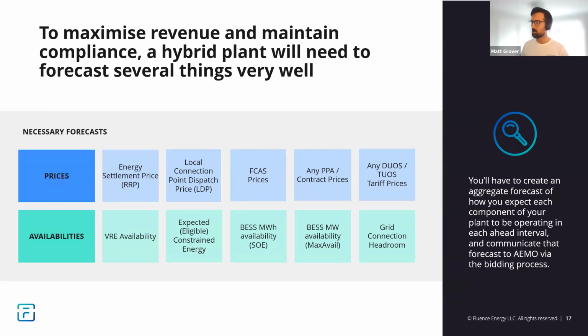One of the main new aspects of hybrid plant operation is that many hybrid plants are going to share a grid connection. So you might have a 100 megawatt grid connection with a 100 megawatt solar farm and a 100 megawatt battery behind the grid connection. How you manage that limited headroom and the availability of those two assets, to make sure you're managing them optimally and compliantly, and not doing silly things like trying to make them violate the headroom constraint, will be super important. And you're going to need a bidding system that will be continually forecasting availability and signaling and re-signaling it through to AEMO for the whole dispatch horizon, call it 24 hours ahead of time. So availability forecasting is going to become even more important than it is today.